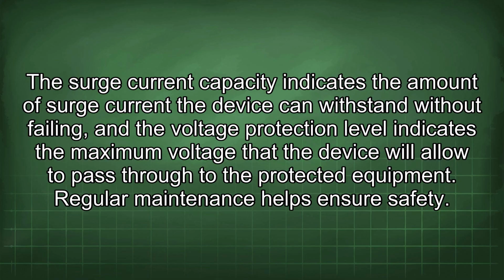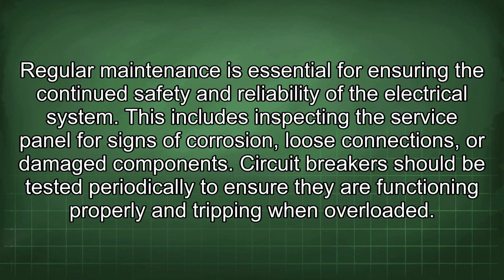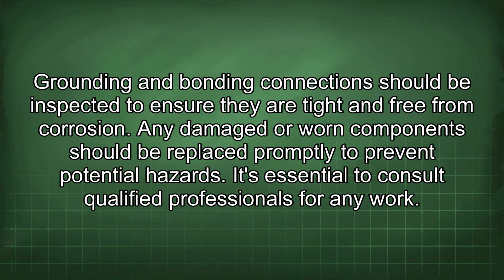Regular maintenance helps ensure safety. Regular maintenance is essential for ensuring the continued safety and reliability of the electrical system. This includes inspecting the service panel for signs of corrosion, loose connections, or damaged components. Circuit breakers should be tested periodically to ensure they are functioning properly and tripping when overloaded. Grounding and bonding connections should be inspected to ensure they are tight and free from corrosion. Any damaged or worn components should be replaced promptly to prevent potential hazards.